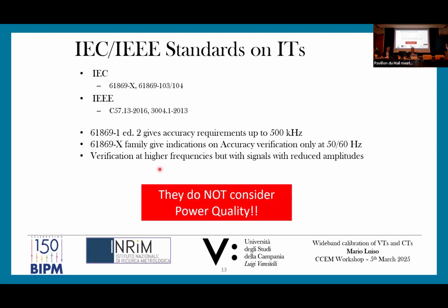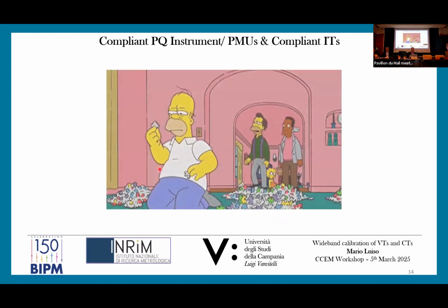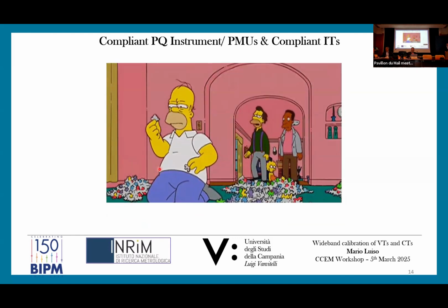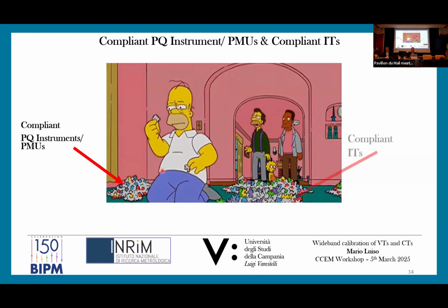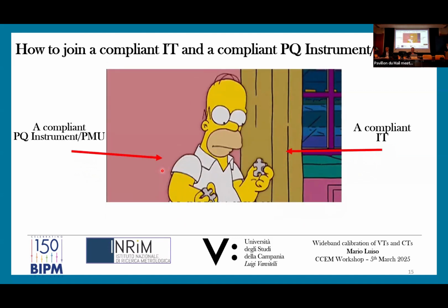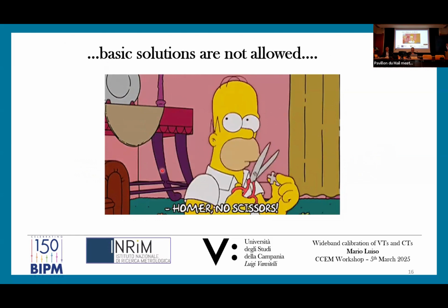So we are in the strange situation. We can buy on the market a compliant instrument for power quality measurement, a compliant instrument transformer, and if we join these two devices, probably we will not get the performance we will expect. So, joking on this topic, it is like Homer Simpson that wants to build a puzzle starting from two sets of pieces. A set that contains compliant power quality instruments, another set that contains compliant instrument transformer. How to join a compliant instrument transformer and a compliant PQ instrument? Unfortunately, basic solutions are not allowed.